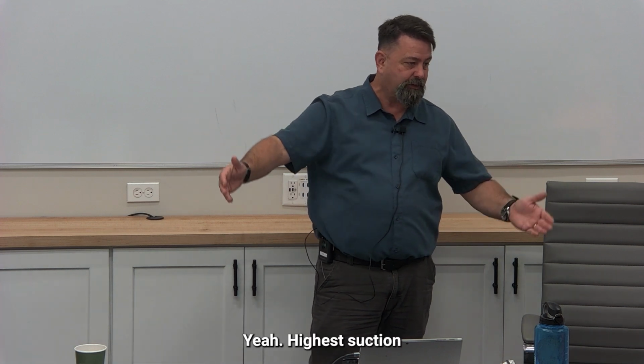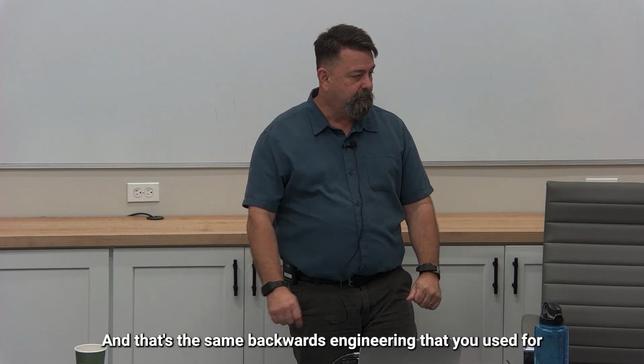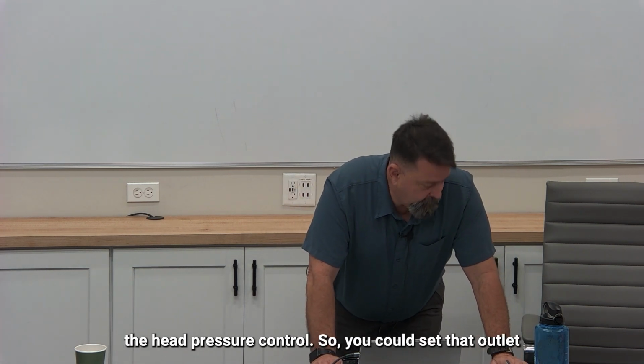So when we have those low ambient problems and we've got cases running warm in the store because we don't have enough discharge pressure, where's that happening? That's happening under 90 PSI, all right? Well, that means this outlet pressure regulator, we're always going to set it at least 90 pounds over our highest suction. Now, when I say our highest suction, we haven't got into EPRs yet, but I'm talking about the highest EPR on the rack, because the differential for the TXV for that case needs to be at least 90. And that's the same backwards engineering that you used for the head pressure control.